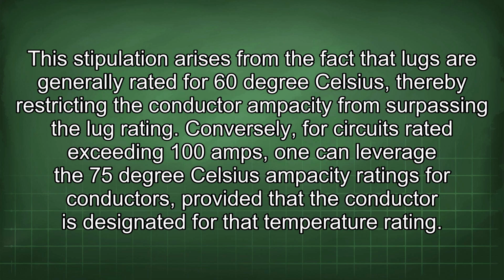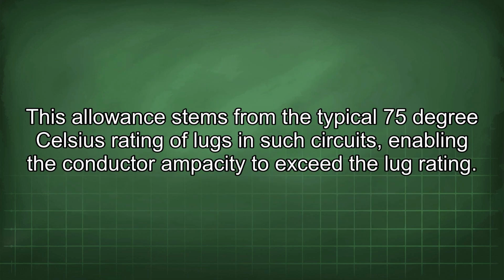Conversely, for circuits rated exceeding 100 amps, one can leverage the 75 degrees Celsius ampacity ratings for conductors, provided that the conductor is designated for that temperature rating.